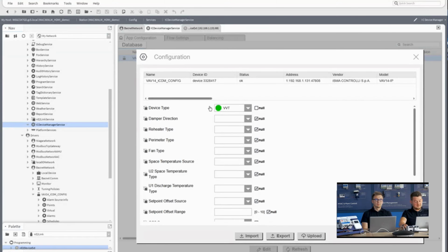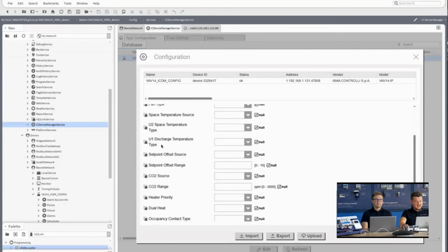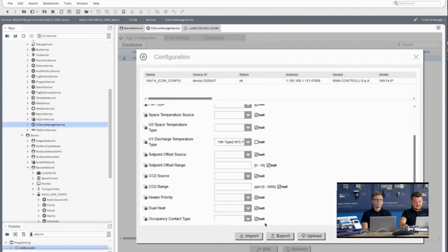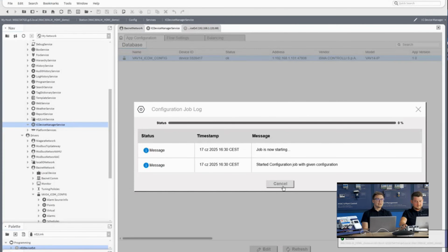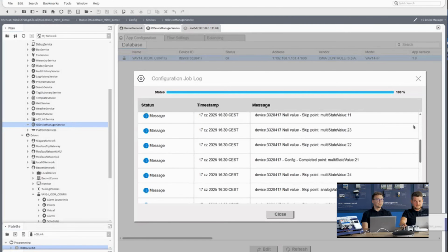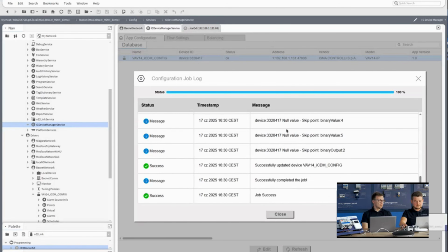So I can change the type from the VAV to the VVT, and let's say I can change the discharge temperature to the 10K type 2. I can upload it to the controller itself, or I can export it, and it's also interchangeable. So I can take the configuration from the iSMA configurator and reuse it directly in the Niagara IC Device Manager. So it's the same file. The same file can be loaded in the iSMA configurator and IC Device Manager.